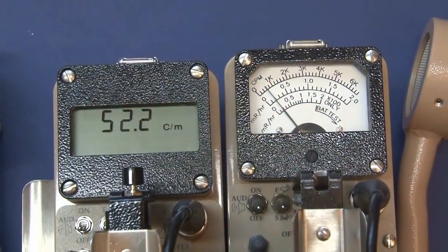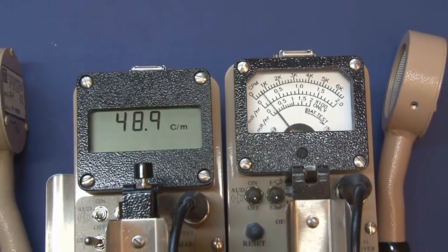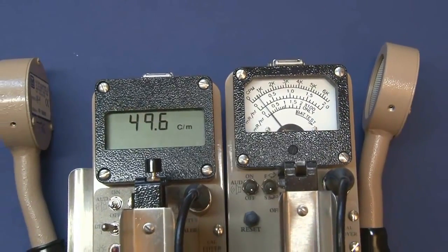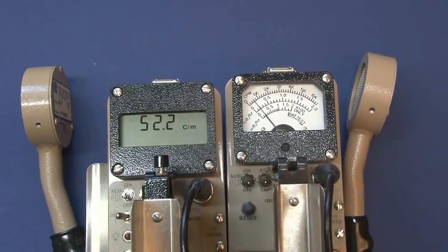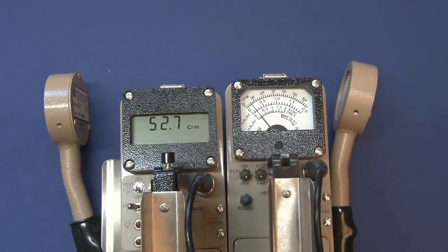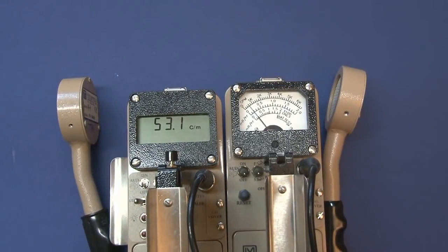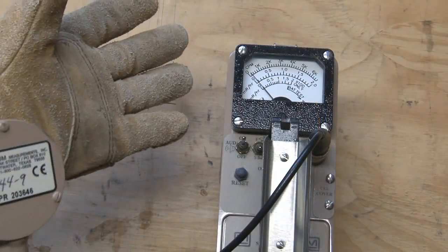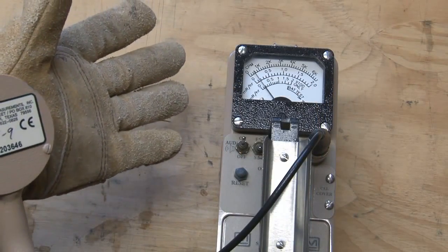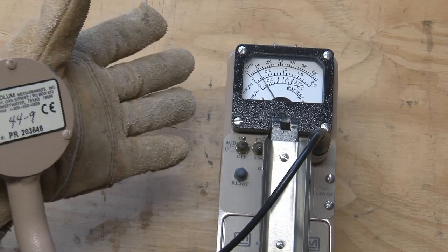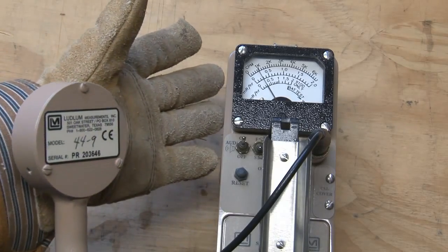Typical background with this type of detector is going to be about 50 counts per minute or 50 CPM, somewhere in that range. While you're surveying, you want to listen to the audible count rate and pause anytime you hear an increase above background to make sure you give that instrument adequate time to respond.